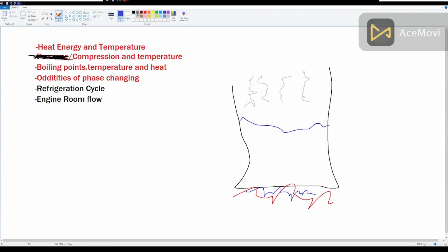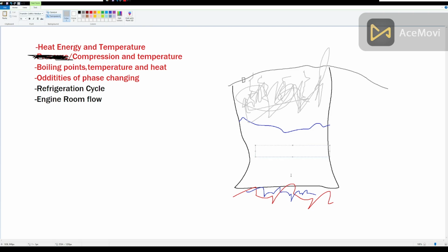Now, if you were to put this under pressure by putting a lid on it, and most lids that go on a stove have a little hole cut in them. There we go. If I was an artist, I wouldn't be doing this. So, if you start to increase that pressure, you will notice something. With the increase in pressure comes an increase in temperature. And this is where you would need to reference a PT chart or simply Google temperature of X psi water, or the heat of vaporization of X psi water.